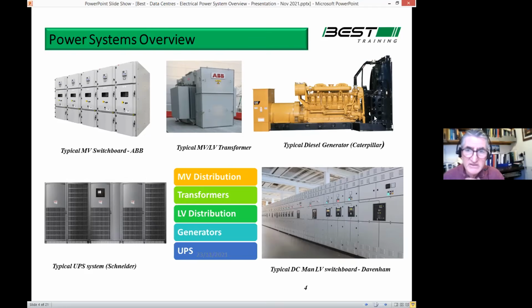The generator, that's a typical generator there. You can see the diesel engine is in the middle. It's just the same engine that you have in a big truck or anything like that. Radiator on the end of it, and then it's driving the alternator on the left-hand side. The alternator is just literally a synchronous motor, if you like, and when it's powered by an external source and given some field current, it generates voltage. And that's the generator. And then the UPS system here, this is what we call a static UPS system. It's stationary. There's no moving parts other than the cooling fans in it. So it converts DC power to AC. So it takes battery power and converts it to AC and gives you a short-term backup while the generator is starting up.